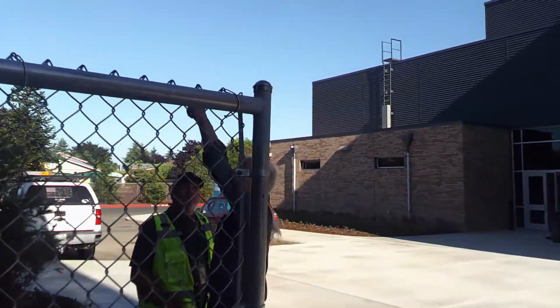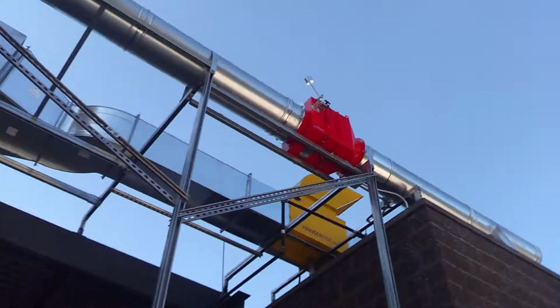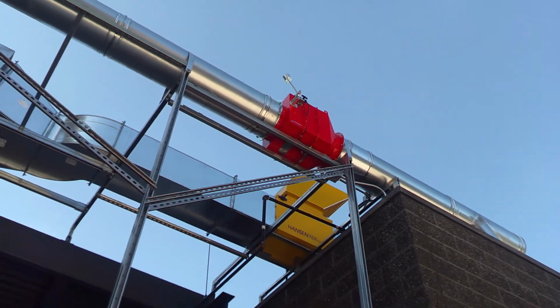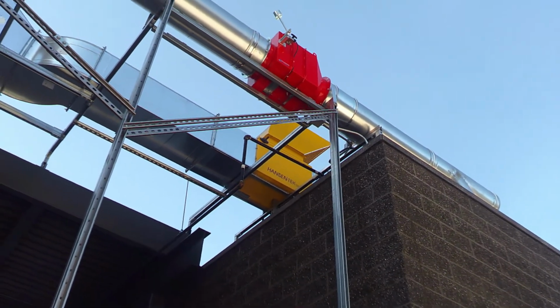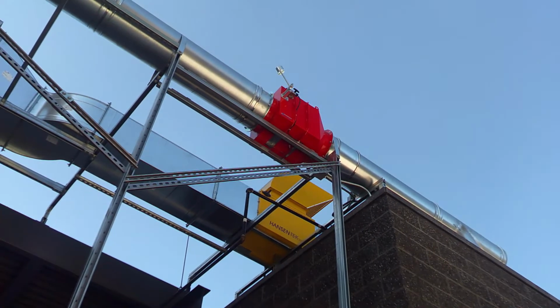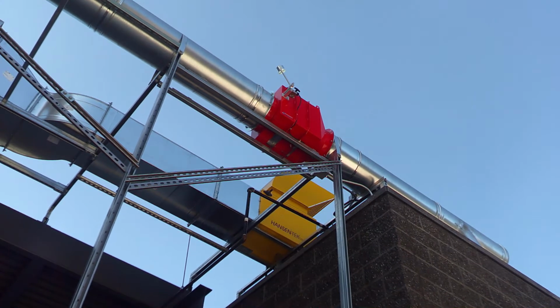Now, see that counterweight? Sure enough. So the damper is basically in line with that handle going down. Looking at it, it's literally blocking a significant part of the duct right now. But it's pivoted on the shaft. The counterweight is to sort of equalize the weight of the damper, so that it's sitting there floating like this. Here's the bottom of the duct, here's the bottom of that damper, and there's a space, and it's quite restricted. But it doesn't really restrict the whole system very much.